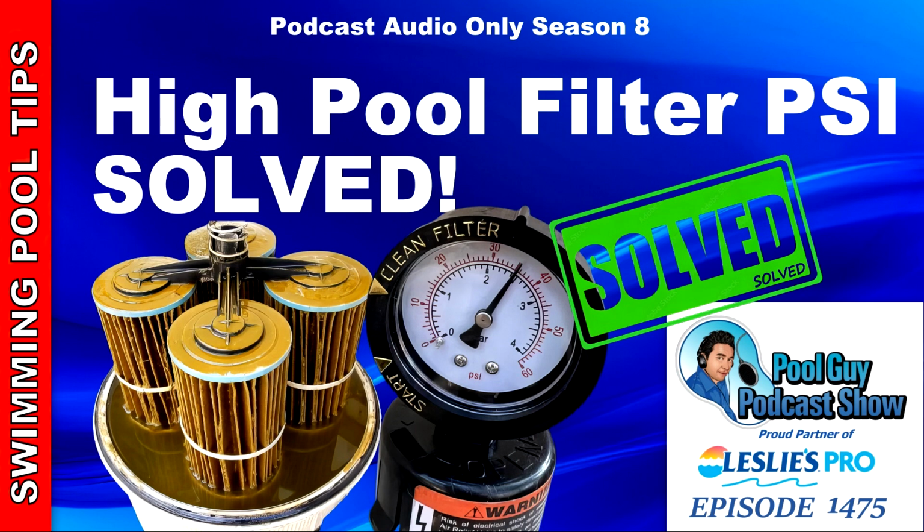Now I know I'm spending a lot of time talking about filter problems, but that's usually the case when you have high filter PSI. There's not a lot of other causes besides the filter being dirty. Now there are some causes that fall into the kind of strange realm. One of the first ones is that the pressure gauge isn't working. So of course tap on that thing to make sure that the actual needle is moving, and then you can be rest assured that that's fine.